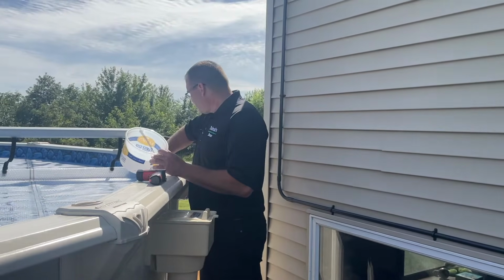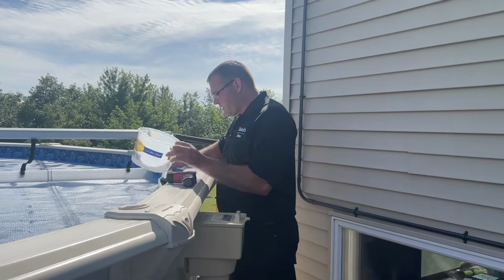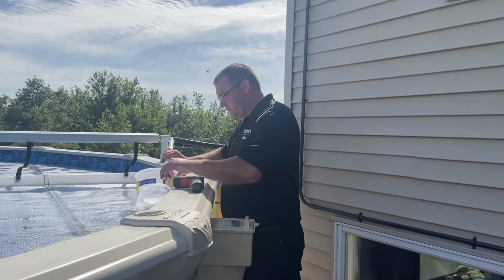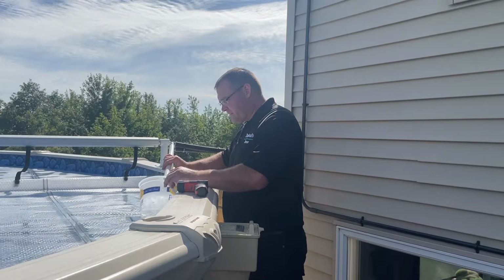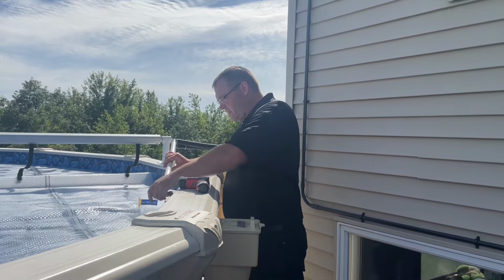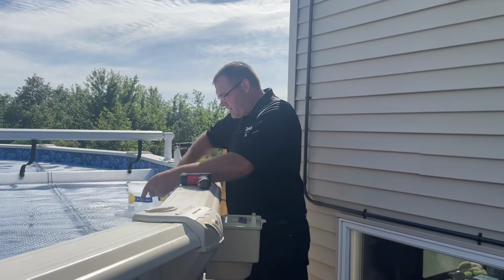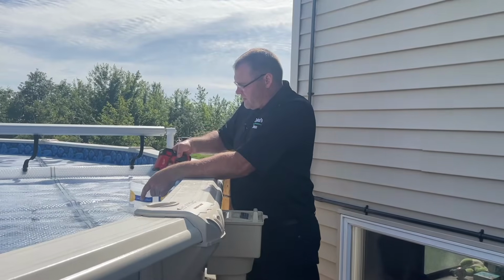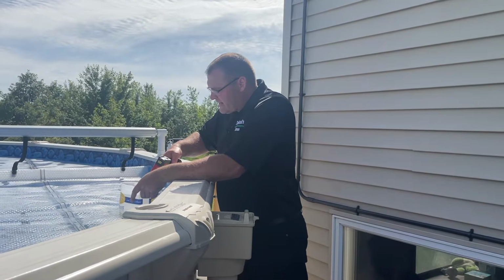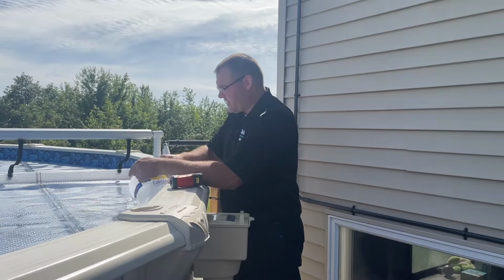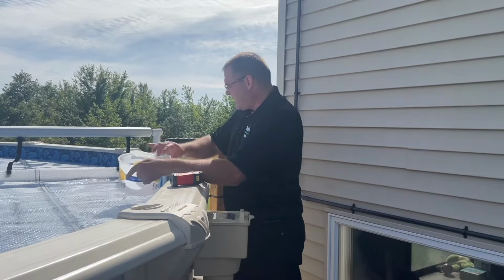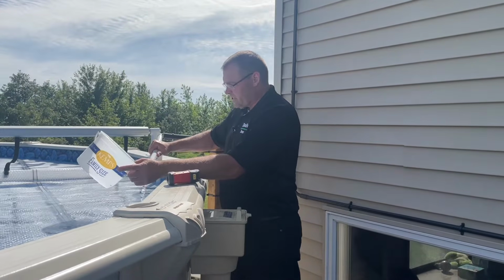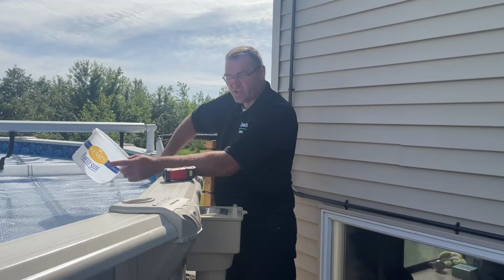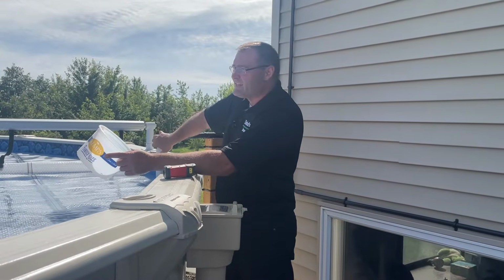So I think this is the shorter one, the auxiliary one that's from in the basement. We'll see what we get here. That one is 92, so we got a 20 degree temperature differential. My judgment is that's probably like 6 or so gallons a minute. So that's decent.